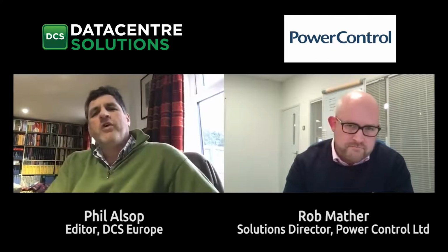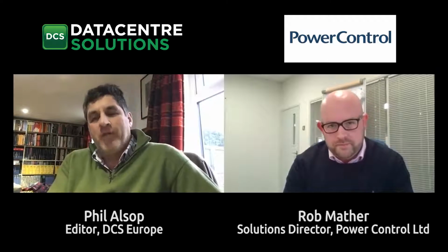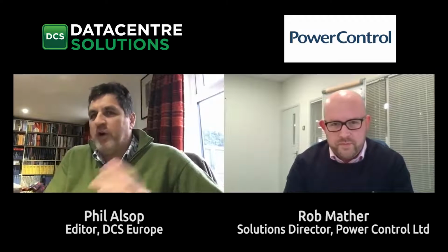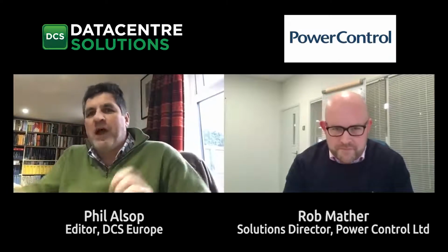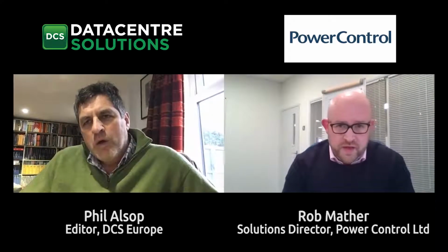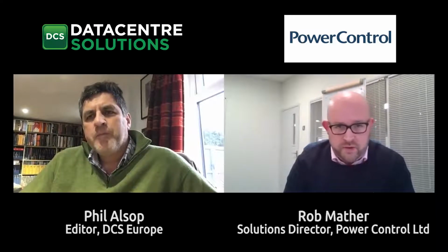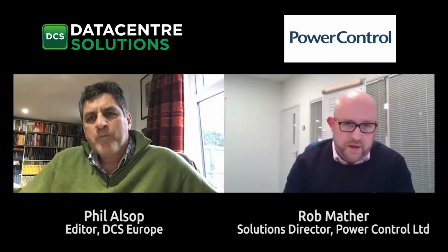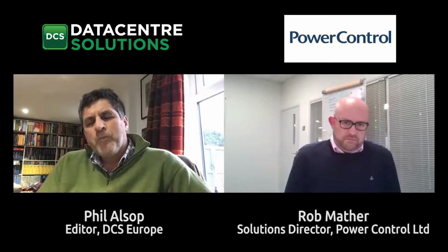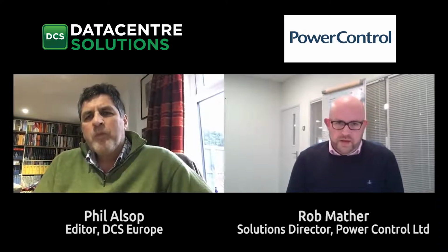And just in terms of the technology, I don't know whether go back 5 or 10 years, what sort of developments have there been that make the actual UPS itself a bit more energy efficient? I don't know if it's adding intelligence to it, different actual design of it, but can you talk us through that a bit? Yeah, so 10 years ago, the majority of UPS would have been transformer based, and so you'd have had all the transformer losses in there. Now they're not included. You don't need the transformer, so that's obviously saved 2 or 3% on your efficiency straight away.